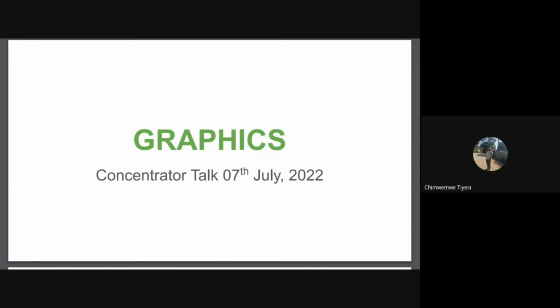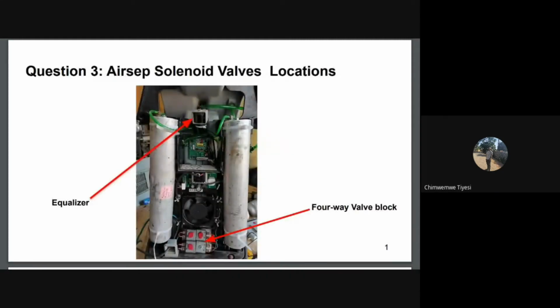Thank you, Maui. The valves for Airsep Intensity 10 are solenoid valves. So by construction, a solenoid valve has a coil. The coil of an equalizer valve has a higher resistance than the coils of other valves on the valve block. For instance, with the 230 volts models of Intensity 10, the resistance of the equalizer valve is 4,200 ohms, and the resistance of the valves on the valve block is 3,200 ohms. What this means is that, supplied with the same voltage, which is 200 volts DC, direct current, the equalizer valve draws less current. It is also important to know that the equalizer valve stays on for less time compared to the feed and waste valves on the valve block.